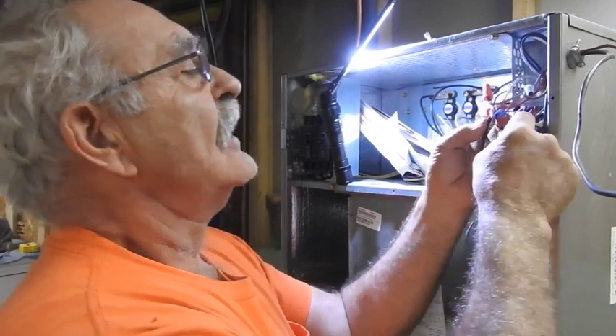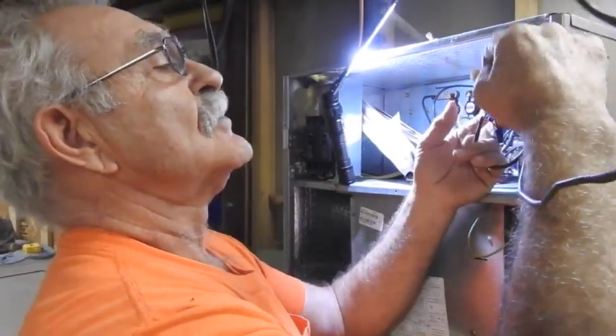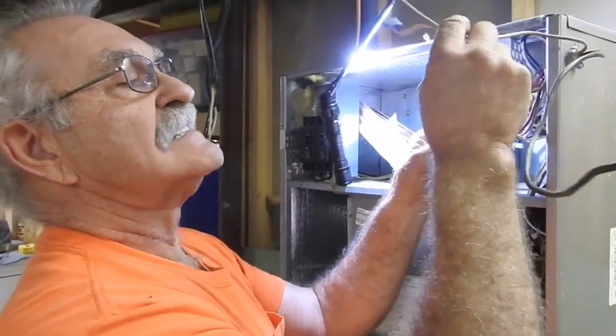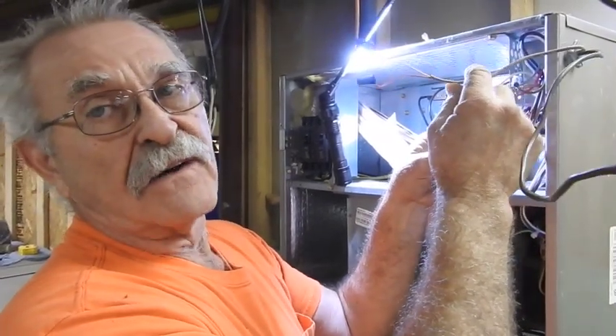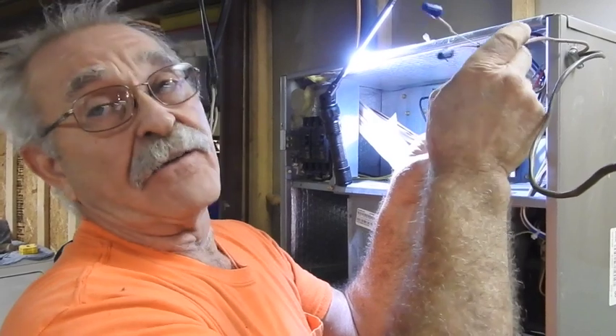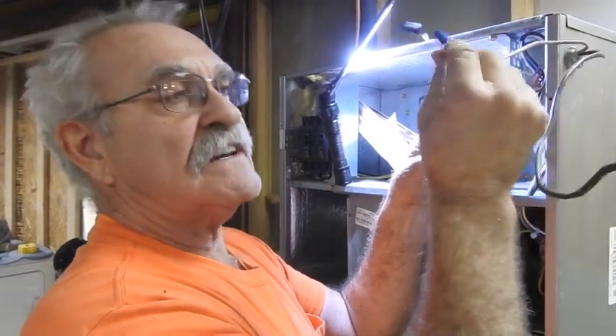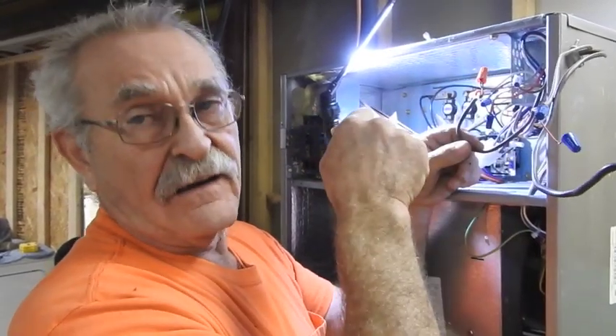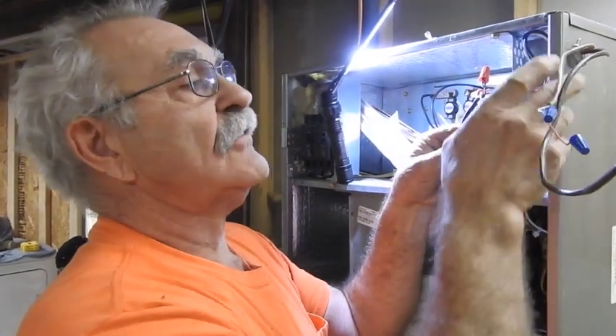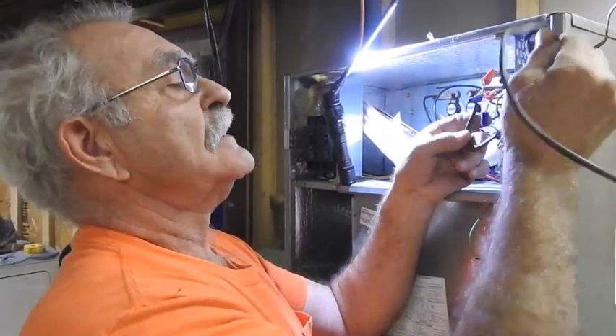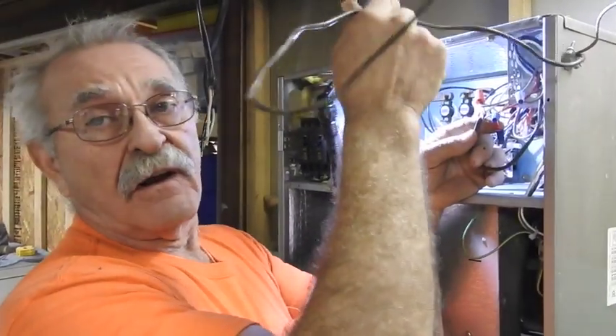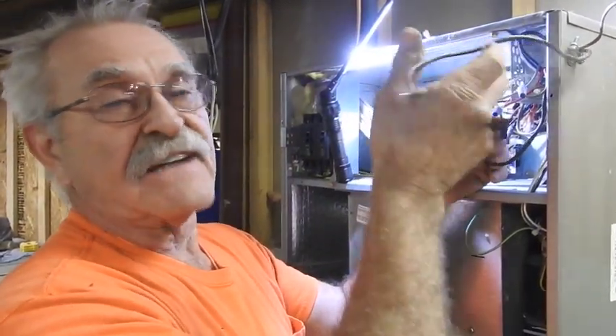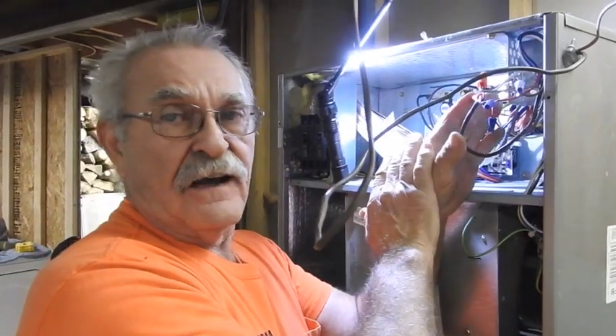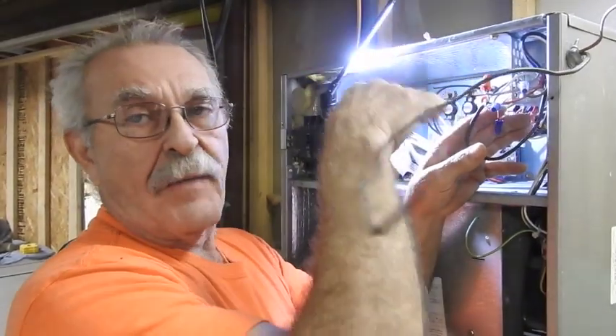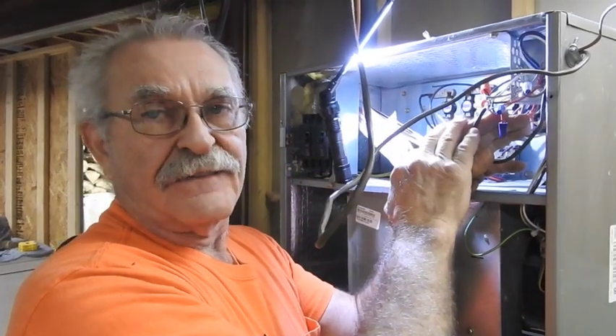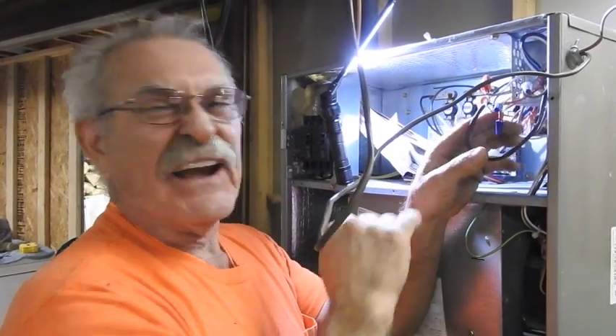So when you go to disconnect, take a quick look at these two terminals - I got cut off there, those were the two going outside, so you can tell immediately with two wires going outside it's not going to be a heat pump, it's just a standard air conditioning system. One of these comes down from the yellow and goes outside, and the other goes to the other side of the transformer. These four wires here are the power up to and the switching circuit from the thermostat, originating at the terminal board, going up through, coming back down to the controls, and then back to the terminal board. Make sense? I know it's clear as mud, huh?